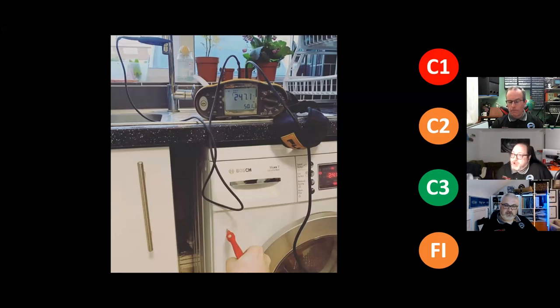So what do we see here? We've got one probe on a tap, which is providing a 0 volt reference of earth, correct? Yes. It's basically a fortuitous path via the copper pipes that feed the kitchen. It turned out that the investigation found the builder who did the kitchen had chopped through a conduit. The old conduit in the building was the CPC, because a lot of old buried conduits did act as CPCs. He had obviously done a repair and reinstated it, but hadn't reattached the earth. So there was obviously a fault in the machine somewhere, and when he put his direct contact probe across the two, he was able to get 247 volts.